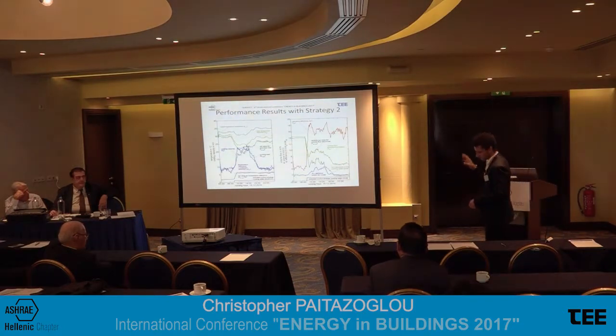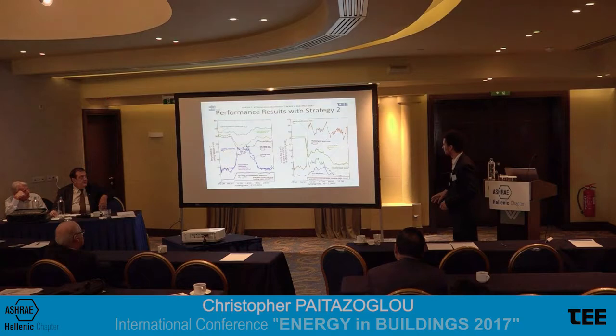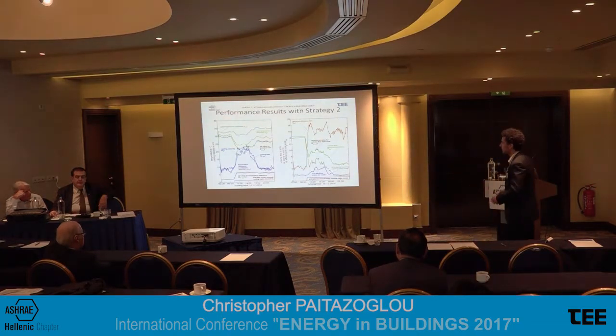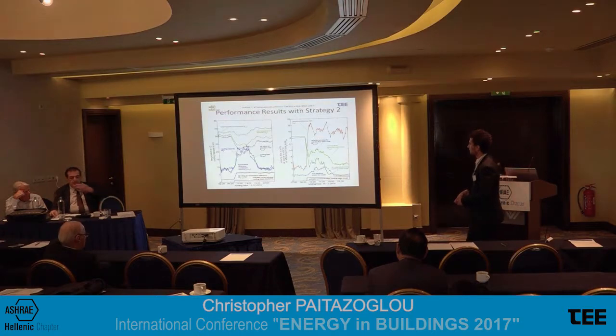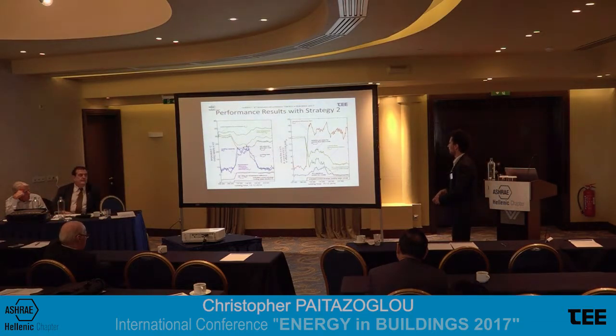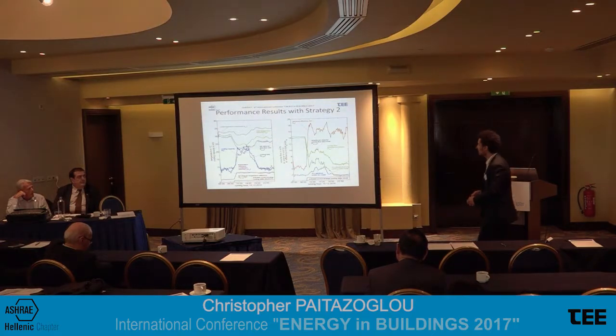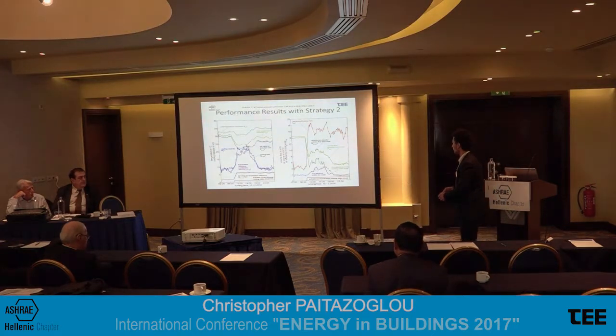Let me give you now a short performance result of how the chiller operated when we activated the second strategy. We see here a running day in December last year, and we see here that the cooling load of the building is at 10 kilowatts. The temperature inlet and outlet of the condenser leads to a difference of 2 Kelvin, and the volume flow is here at 40 cubic meters per hour, and the COP, the electrical efficiency, is at a low level of 4.